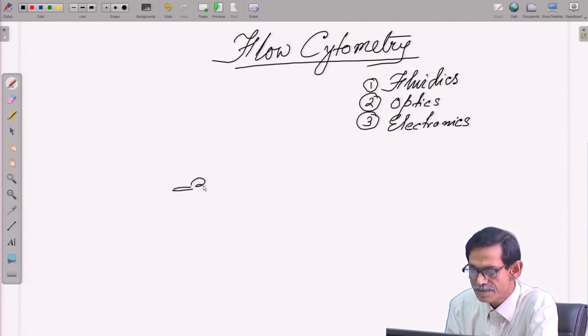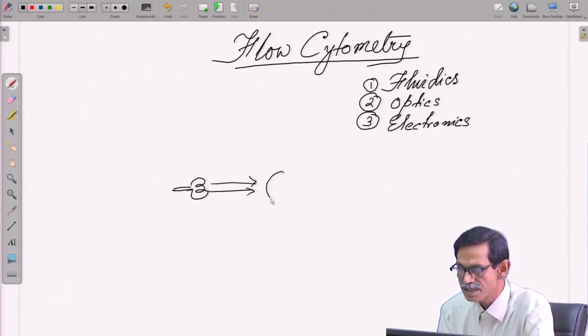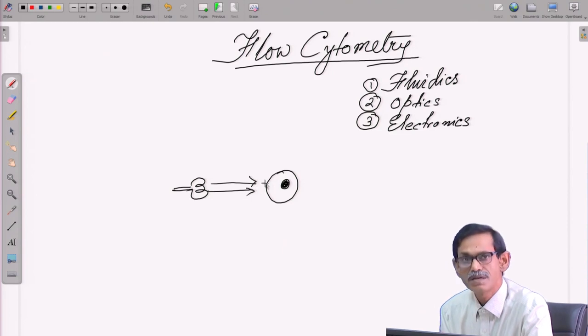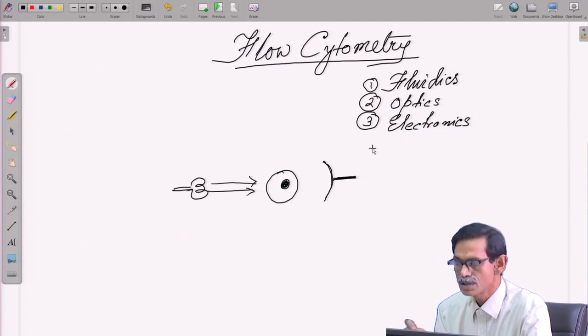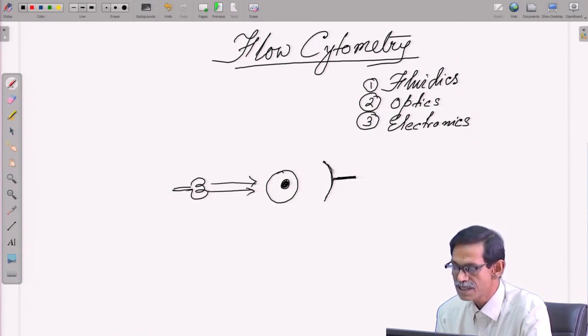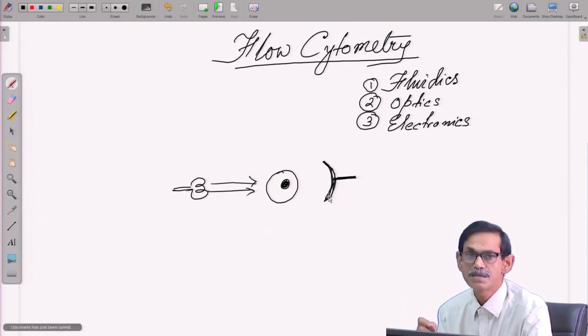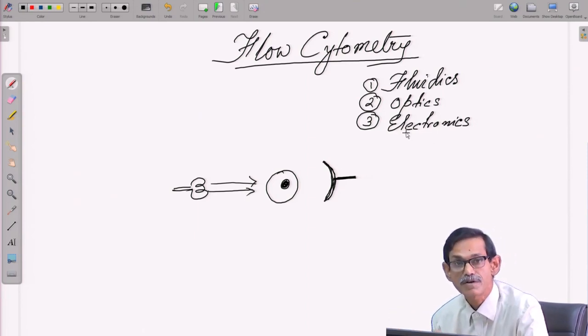There is a light source. Light is going, and in the path of the light, if there is a cell — suppose this is a nucleus — this light will interact with the cell and there is a detector here which will detect the signal. The cell comes here by fluidics, optics does its job, and the detector is linked with a photomultiplier tube (PMT), which can amplify the signal if needed. Then the electronics part gets the information and digitizes it.